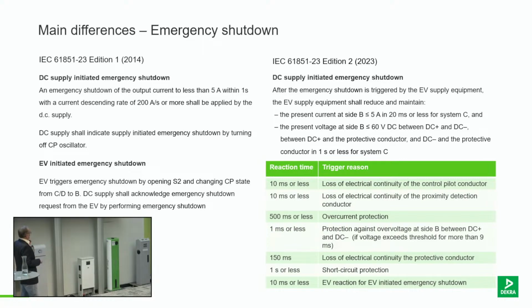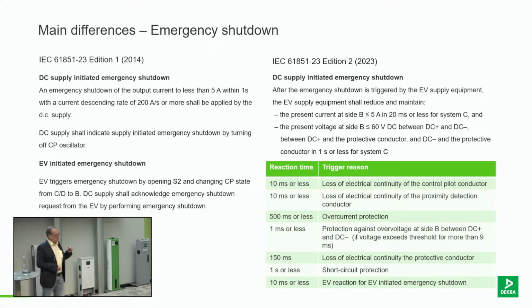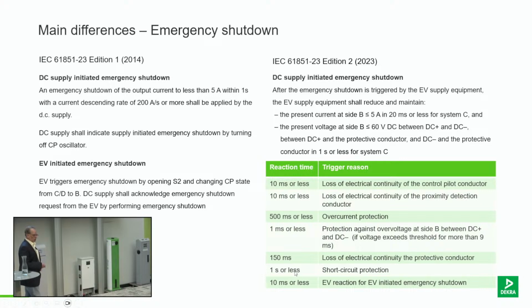Other problems which we observed in the market, and which have now also been clearly addressed, is the fact that chargers sometimes need to shut down for emergency reasons. And one of the more important shutdown procedures is if the electric vehicle initiates emergency shutdown. So if the EV thinks, okay, something doesn't go well anymore and I immediately need to stop the charging. What we have now is a so-called reaction time of 10 milliseconds or less. And that's a bit different from before. And what it basically means, within that reaction time or trigger time plus the reaction time, there are about 30 milliseconds to make sure the current is below 5 amps and is below 60 volt to create safe conditions.